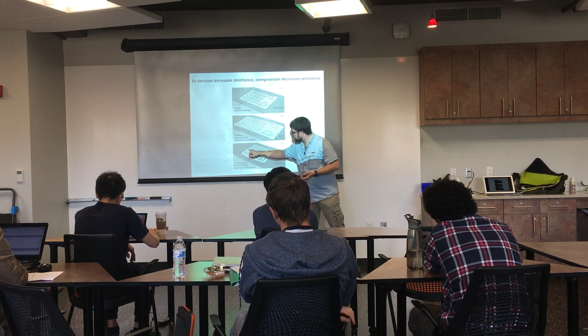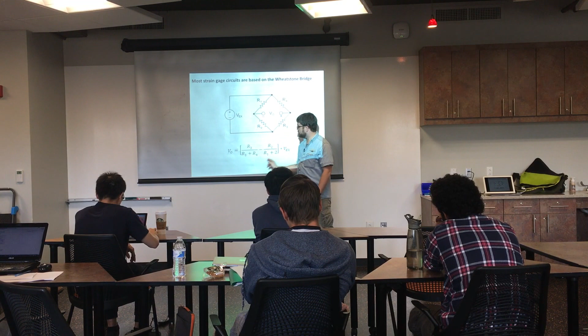Most of the time we deal with a Wheatstone Bridge in some variety, a circuit we've seen earlier that you're going to build next week, where there are 4 resistances. We excite it with some voltage, and then we're measuring a voltage differential inside. This is the formula for the excitation voltage - you know all the resistances, and that tells you the voltage you're going to measure out. So you're generally going to solve that for some combination of the resistances R1 through R4.